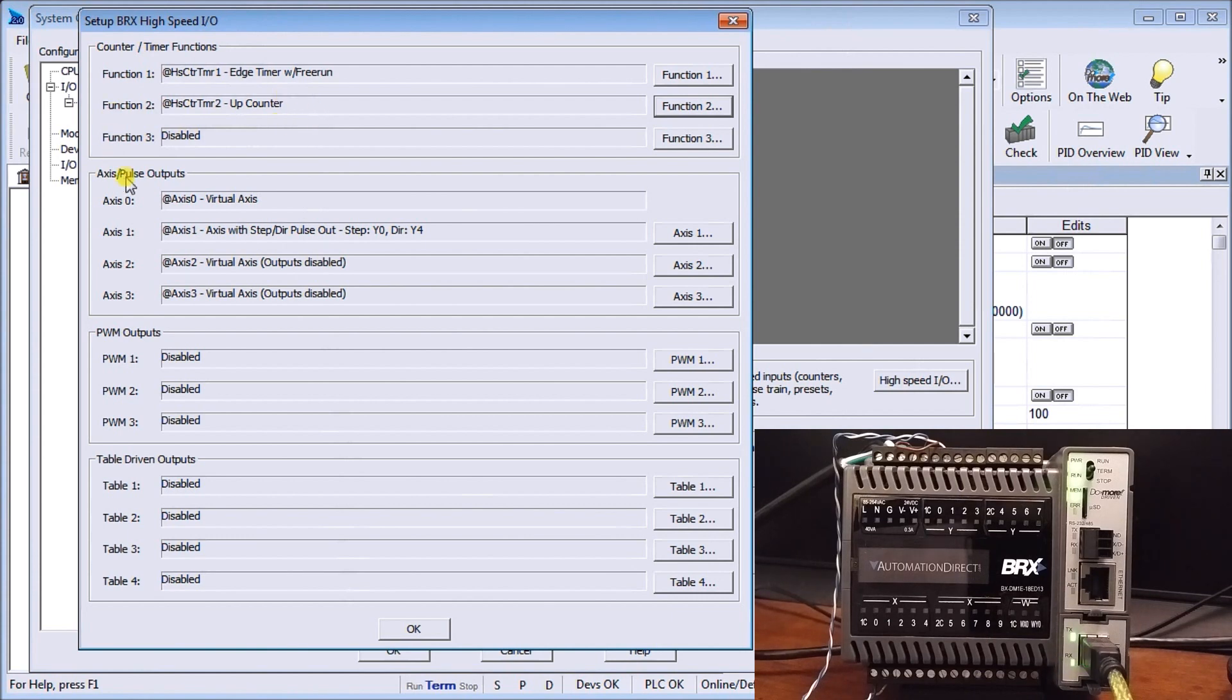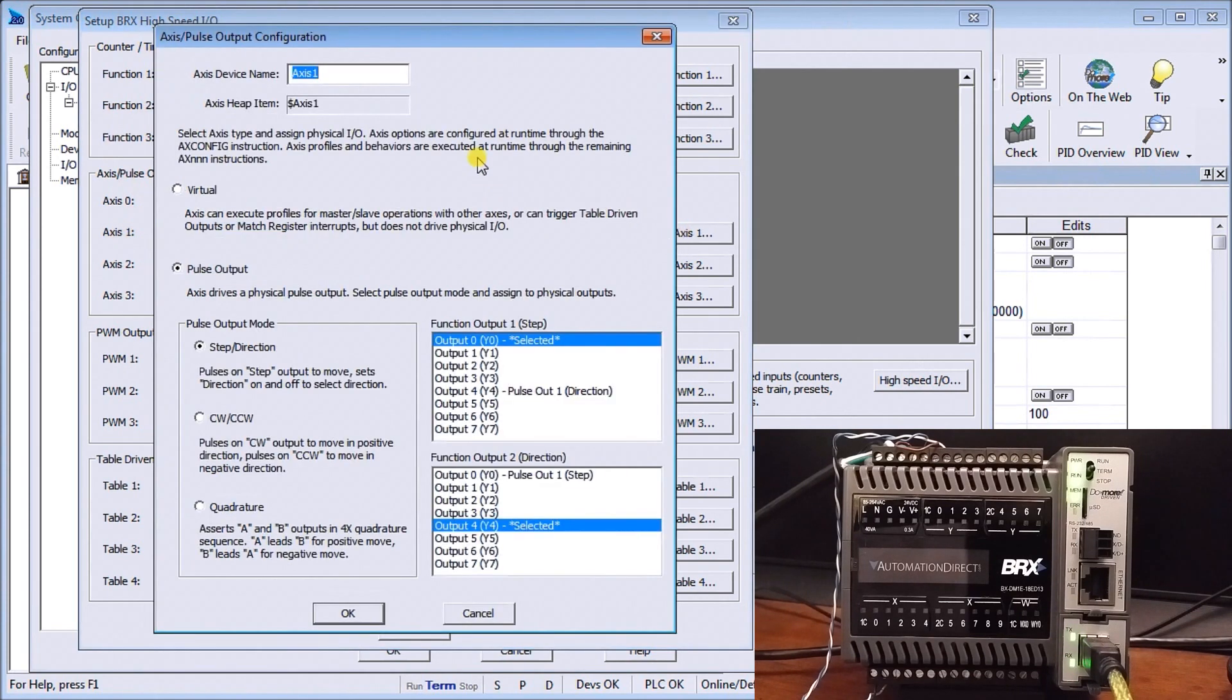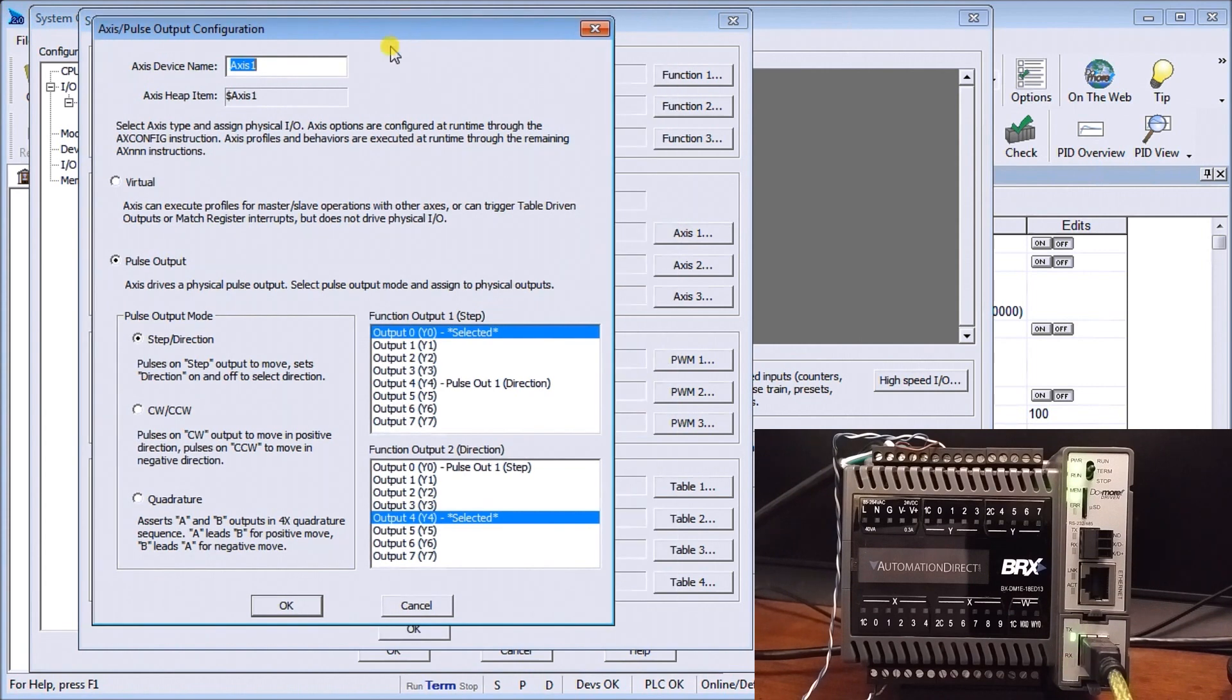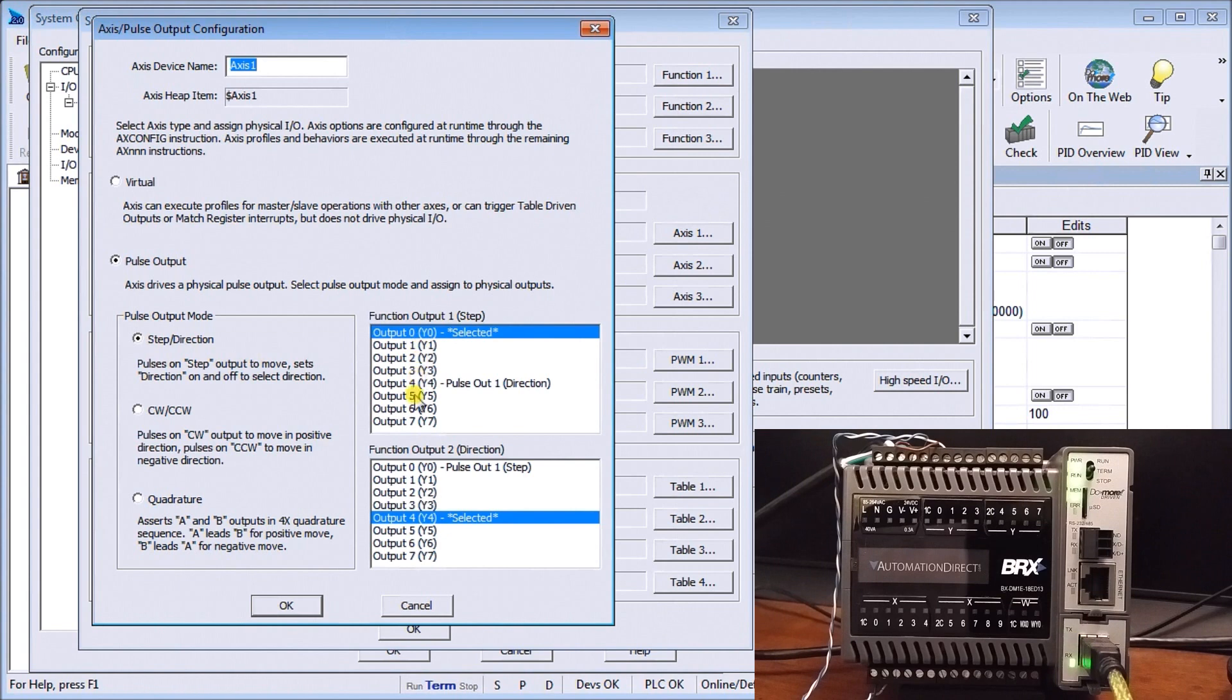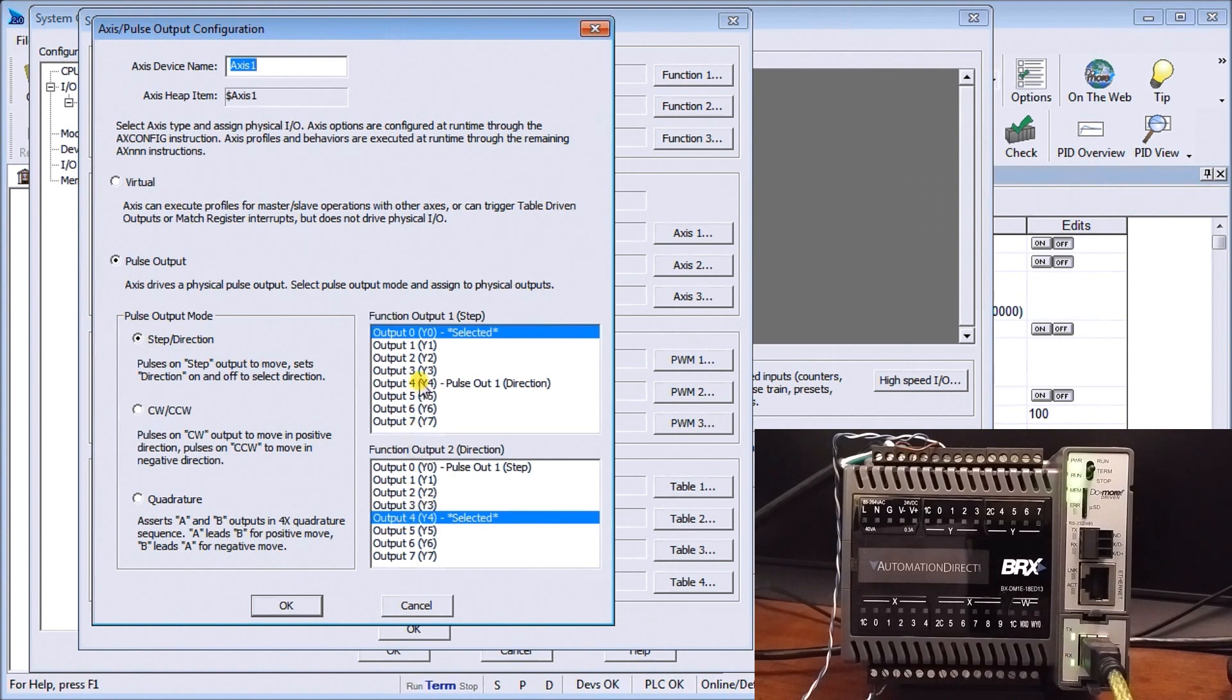Now the last thing we'll do is set up our axis and our axis number one. So we'll take that and what you'll see is we will use a pulse output and we use step and direction. And our step will be output number zero which is what we want here on our controller and our direction will come from output number four. Now I use that to separate it so if I want to use other high speed outputs I could.